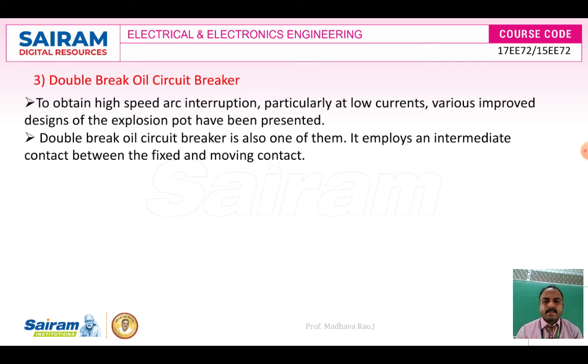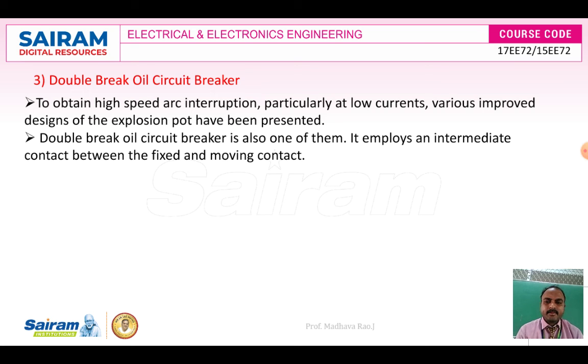In the double break oil circuit breaker, there are two breaks in the circuit breaker. This type provides high-speed arc interruption and is suitable for low currents. Various improved designs of the expulsion pot have been developed, and the double break oil circuit breaker is one of them. It employs an intermediate contact between the fixed contact and moving contacts.